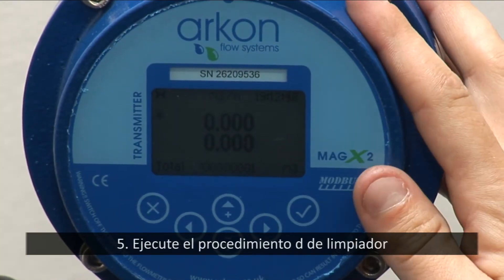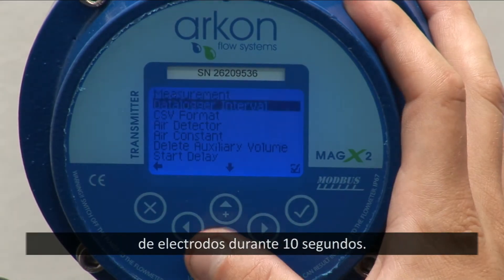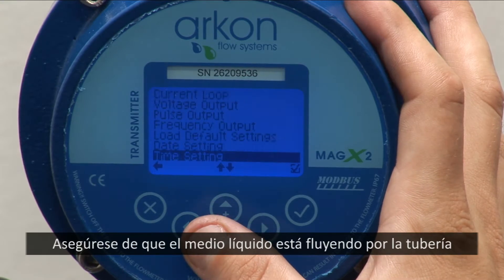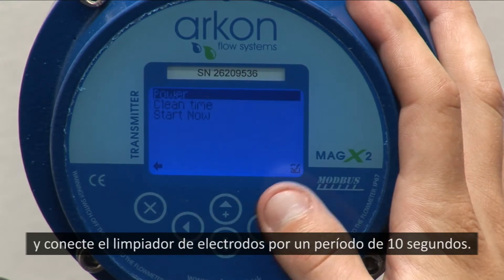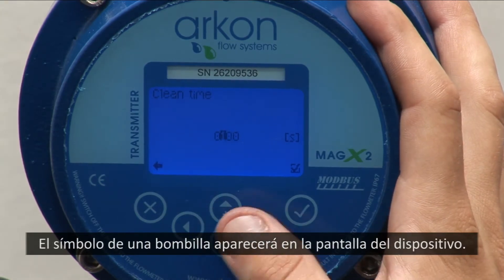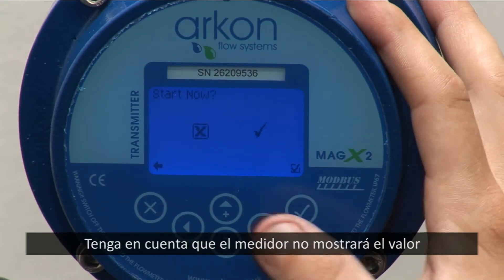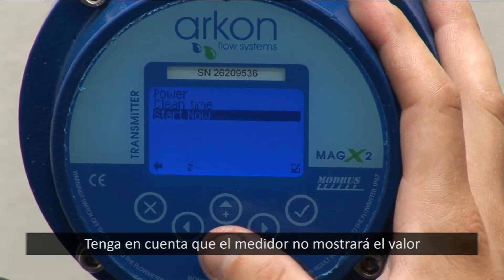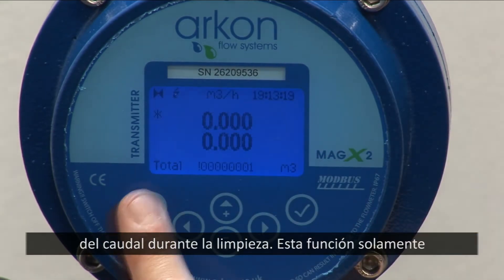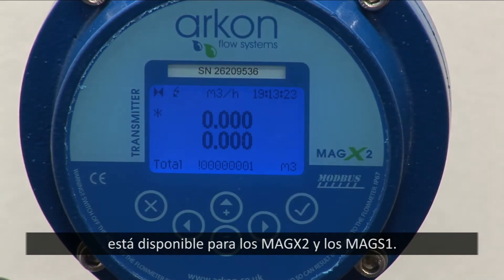5. Execute the electrode cleaning procedure for 10 seconds. Make sure the measured medium is flowing in the pipes and turn on the electrode cleaning for 10 seconds. A symbol of lightning is shown on the display. The meter does not show a flow value during cleaning. Please note, electrode cleaning is valid only for MAGX2 and MAGS1.